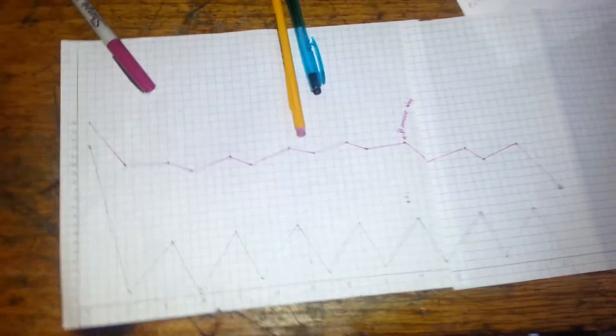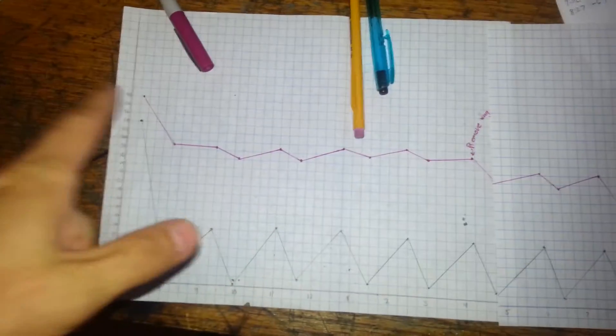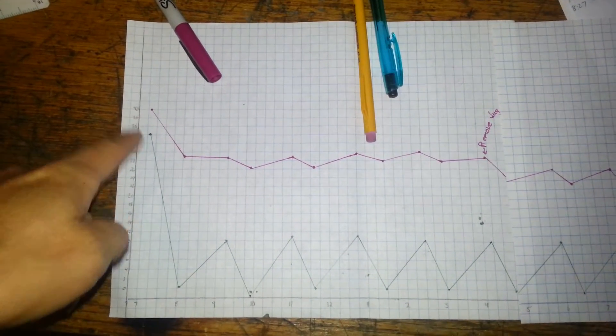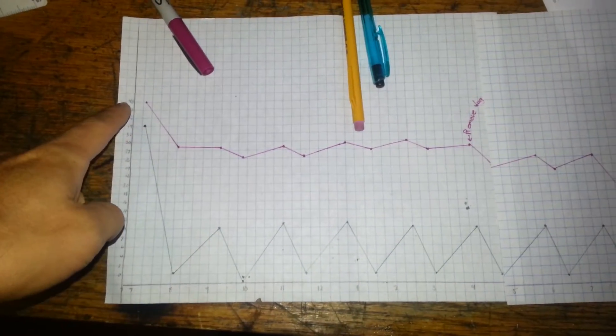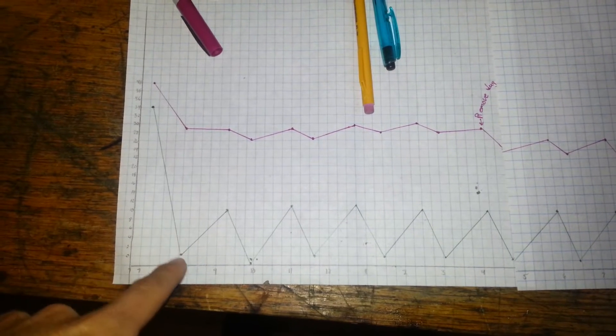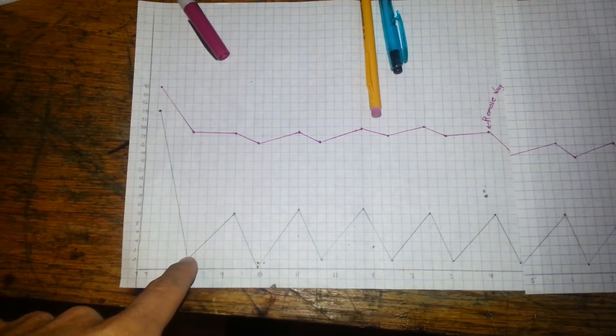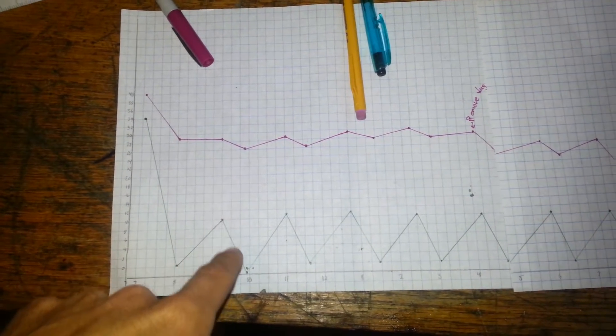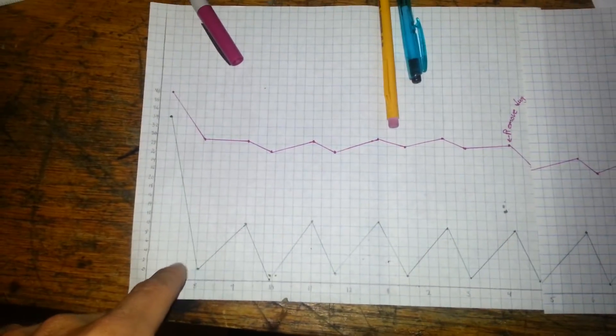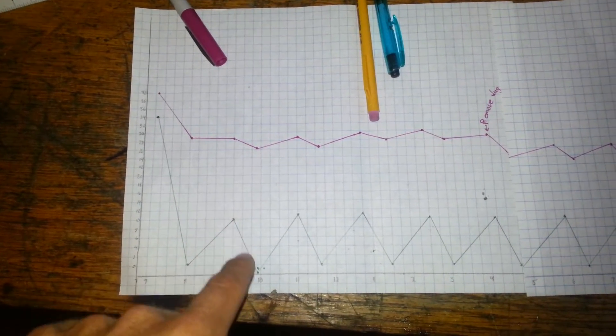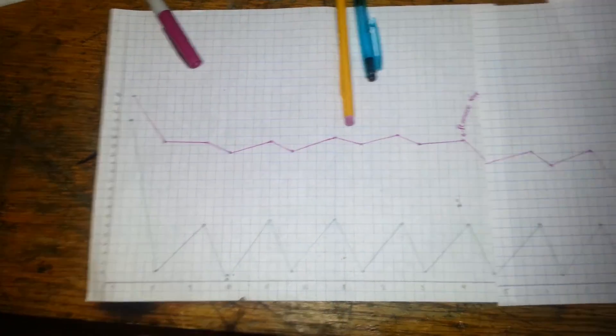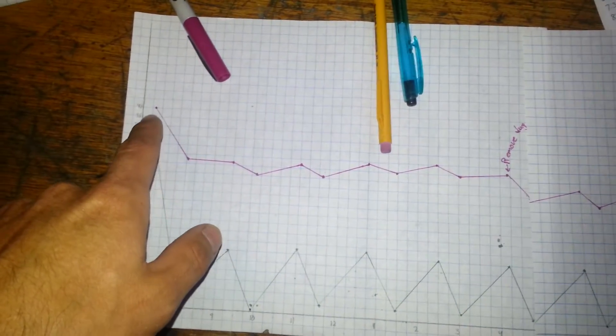I cataloged everything and wrote it out, so it started about 40 degrees here this morning at about 7:30 or something. Dropped the temperature in the glycol bucket down to zero and then allowed it to rise and drop and rise and drop. You can see it does it in a very consistent manner. It's usually off for about an hour and ten minutes and then on for about 30 to 40 minutes.